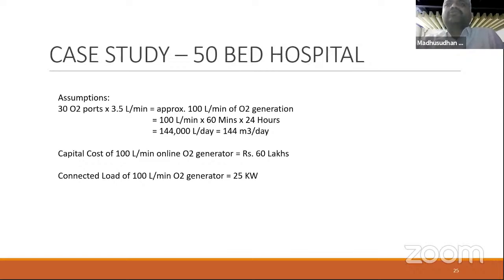So even if you assume 24 hours, 30 ports continuously consuming, you're talking about 144 cubic meters of oxygen requirement per day. Now, something like this, an online oxygen generator would cost you today 60 lakhs, and its connected load will be around 25 kilowatts. These are rough numbers, what I know.